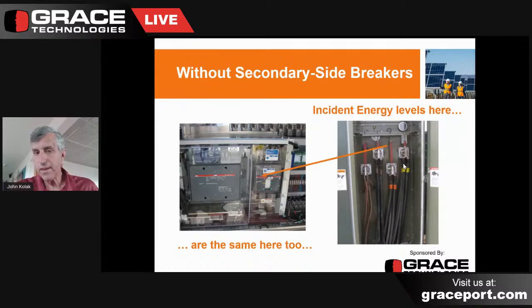So we'll talk about that, but realizing where you take your voltage readings matters from both a shock hazard, but also from an arc flash standpoint that we want to talk about. But do keep in mind that whatever you've got on the secondary side of that transformer, that low voltage side, wherever that comes up in the switchgear, absolutely can represent an arc flash hazard, and it can be very significant.